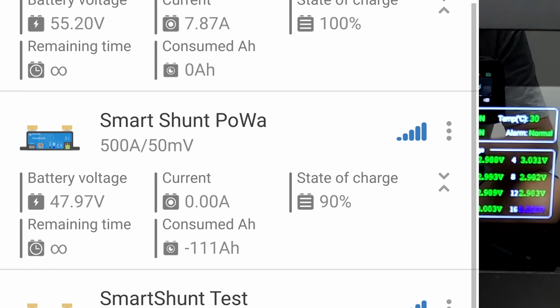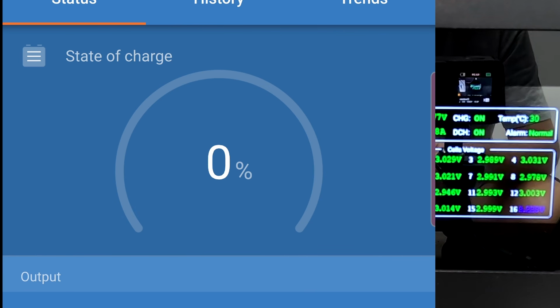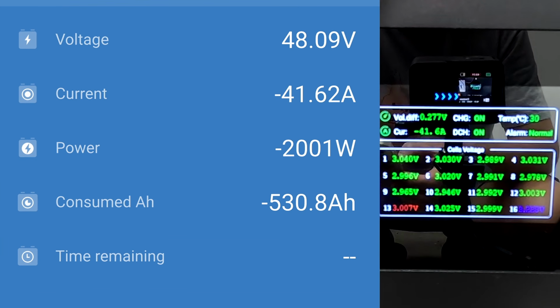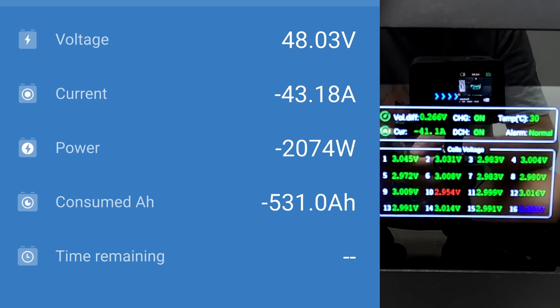Alright, let's have a look at the smart shunt test, which already says 0%. Yes, 0%. 41 amps we are discharging, 2 kilowatt, and we have consumed 530.9 ampere hours already. So we have reached the rated capacity of these cells, which is fantastic.